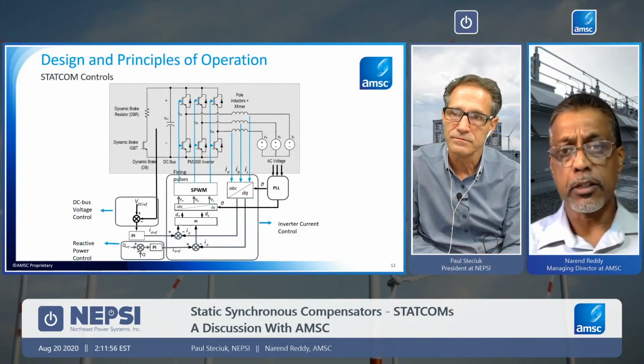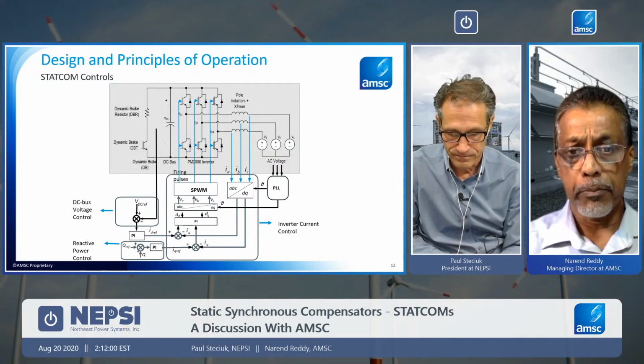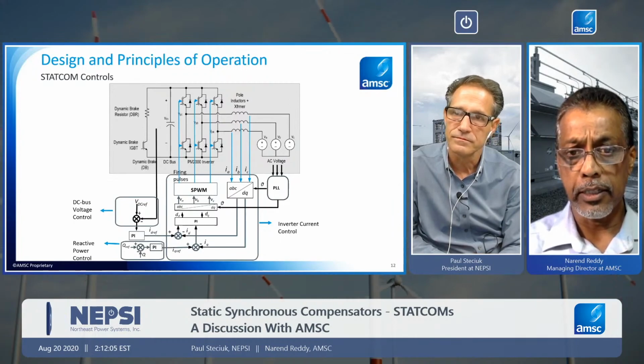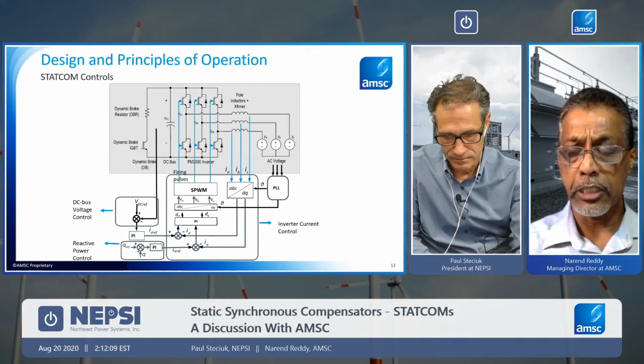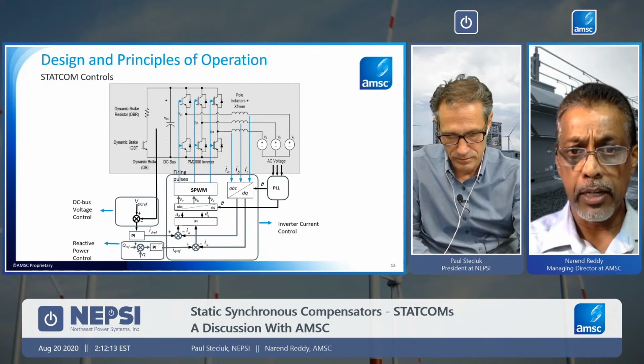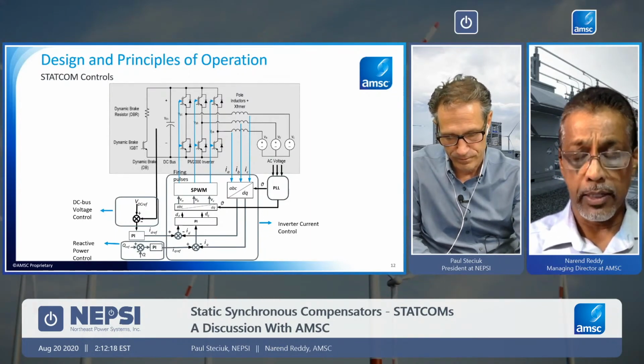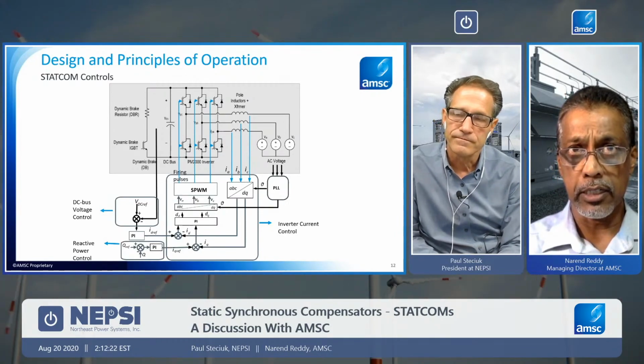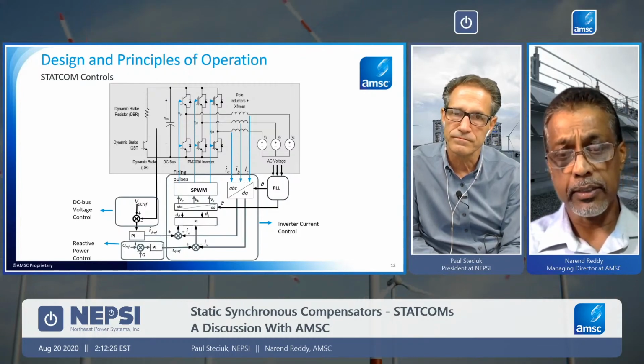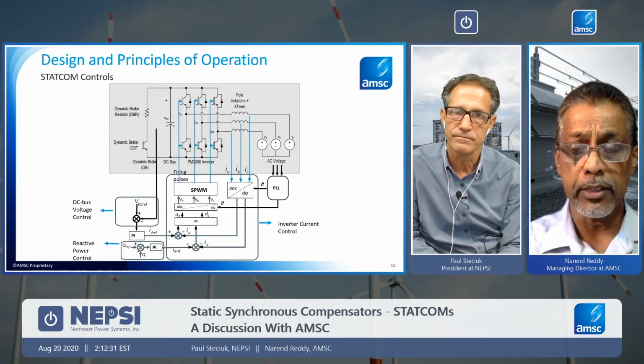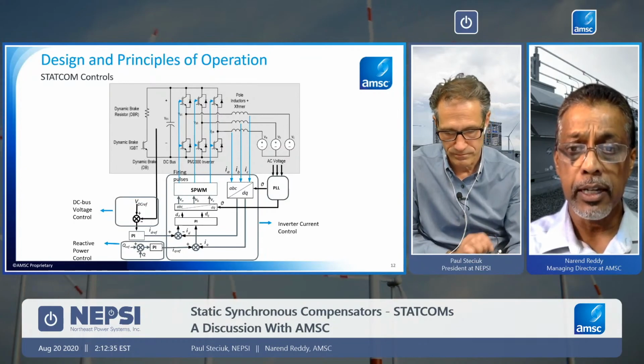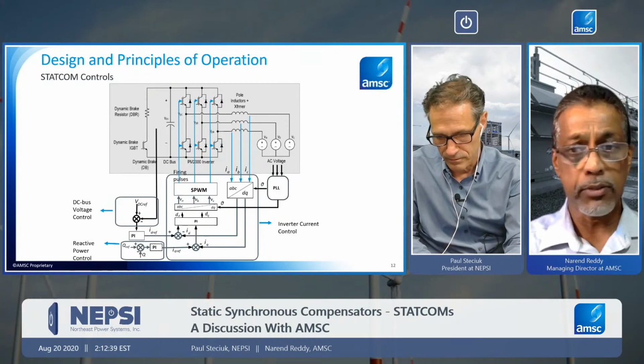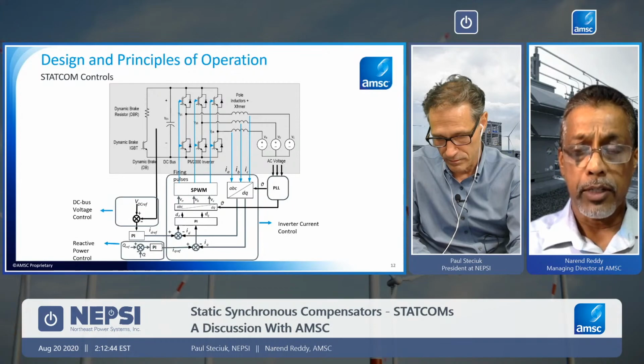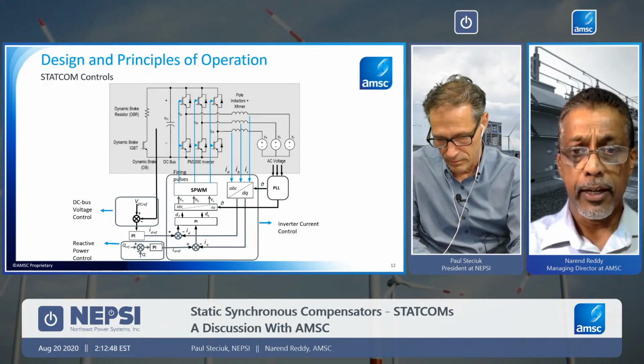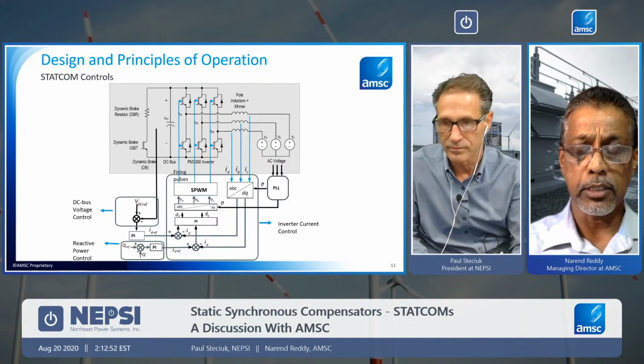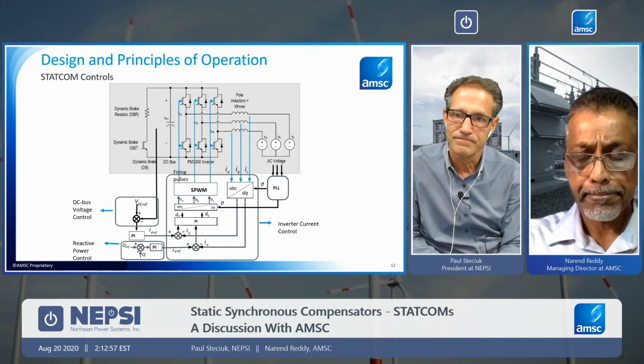So just taking the STATCOM controls, I've shown you the three-phase inverter bridge, but now I'm showing a little bit more detail into the sinusoidal pulse width modulation technique and all of these additional controls that need to go into it in order to make the system operate autonomously on a closed loop basis. One, you need to be able to maintain the internal system voltages and currents within their design ratings. Secondly, you have an objective that you're trying to meet on the system AC side. So you have to continuously monitor either reactive power or the voltages, or whatever the objective may be, as we'll talk about a little later on. All that needs to be fed in, and all these control loops are operating at very high frequencies to make sure that the system overall is doing its job as designed.